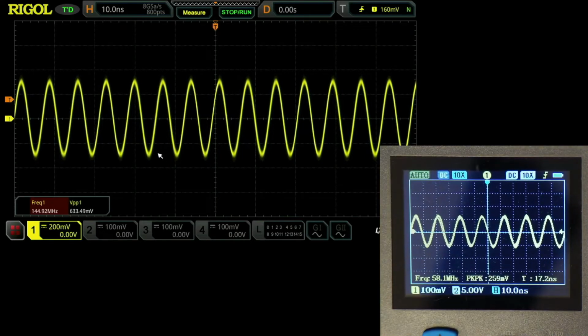so this is about 140 megahertz, and the signal came back, but still it's reporting a frequency of about 58 megahertz, and the peak to peak should be over 600 millivolts, and it's reporting 247. So although you can see that it's a sine wave, in anything above 80 megahertz you really can't trust it, and therefore the bandwidth of it is definitely 80 megahertz and not 120.